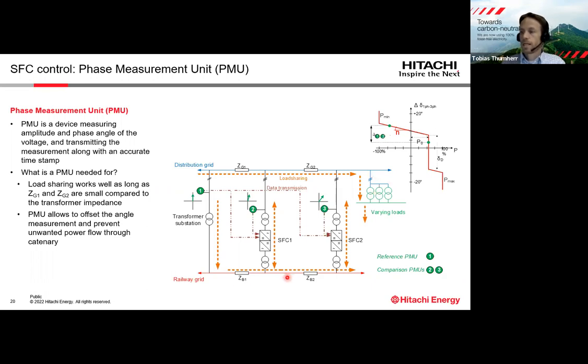So what we can do now with these phase measurement units is that we measure the voltage phase angle here at the transformer substation. We transmit this signal to the 2 SFC substations, and then we add the angle difference between the angle at the transformer substation and at the SFC substations. We add this difference to the characteristic of the static frequency converter as an offset. This then means that the SFCs behave with their characteristic as if they were connected to the same location as the transformer. So with that, we can basically prevent the power from flowing through the catenary system instead of through the distribution grid. So I think in that sense, the phase measurement unit is a very nice tool.